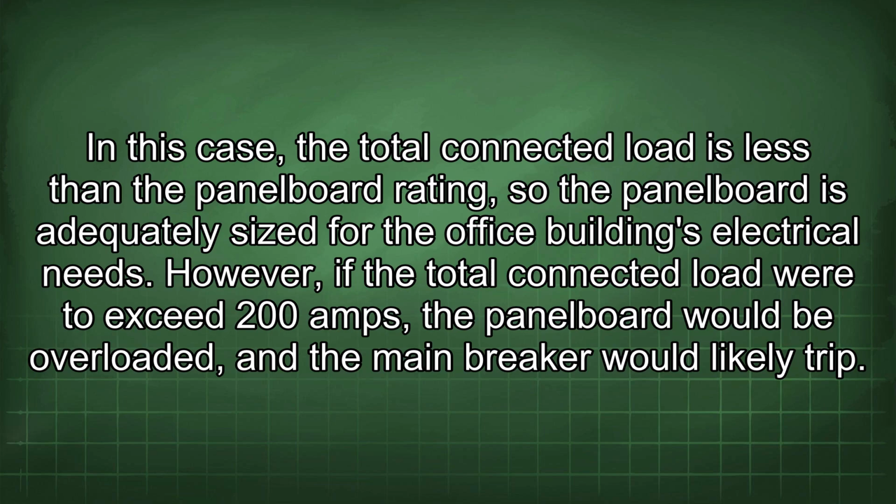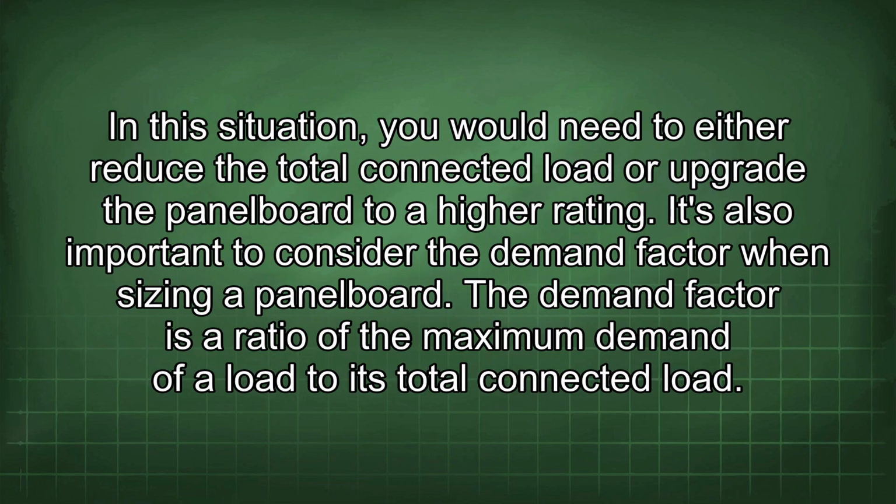However, if the total connected load were to exceed 200 amps, the panel board would be overloaded, and the main breaker would likely trip. In this situation, you would need to either reduce the total connected load or upgrade the panel board to a higher rating.